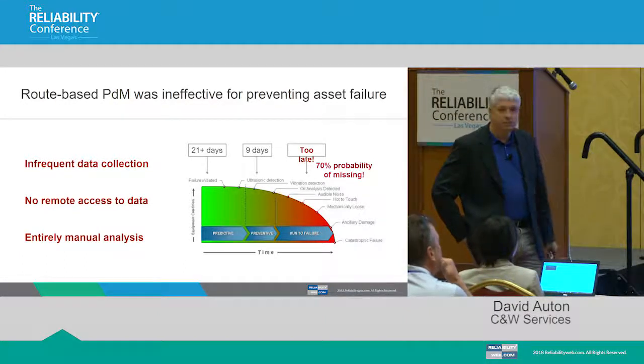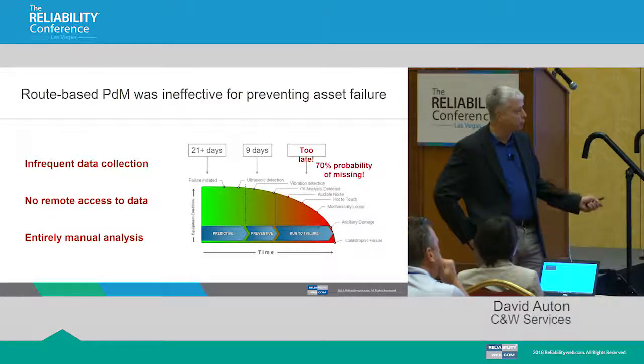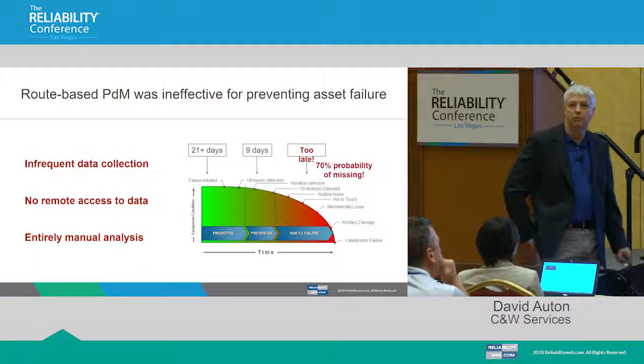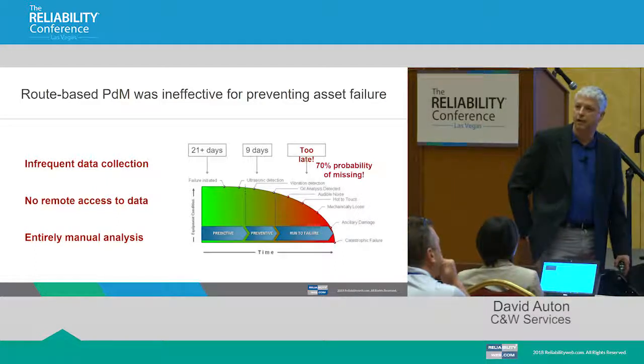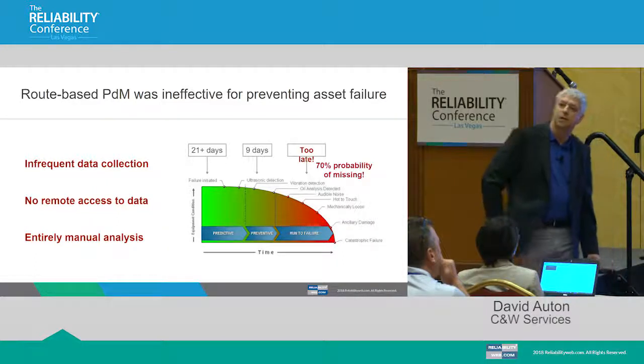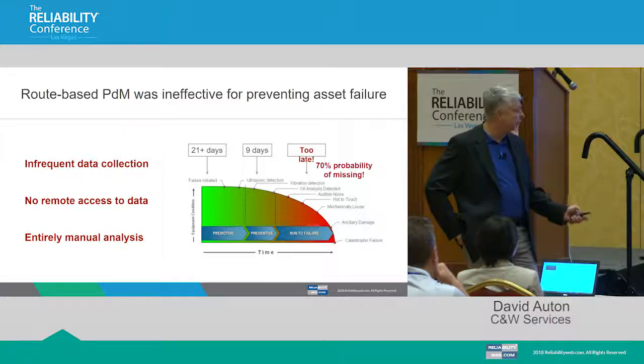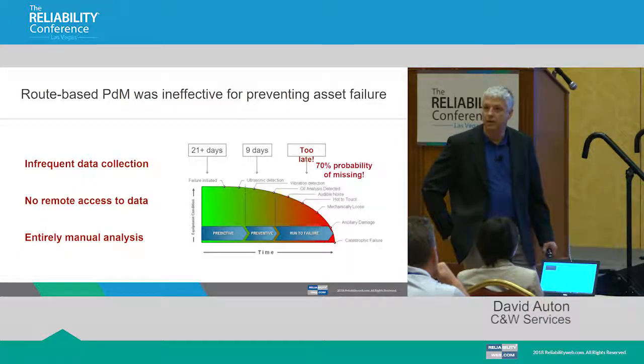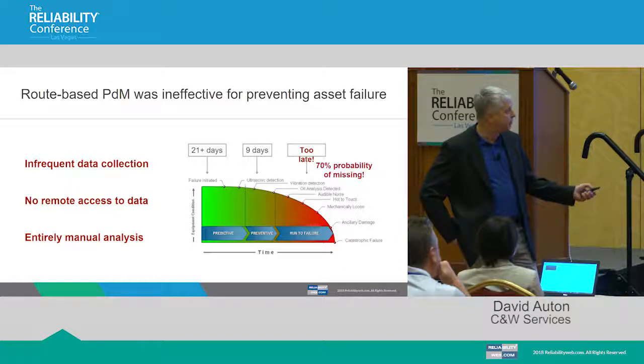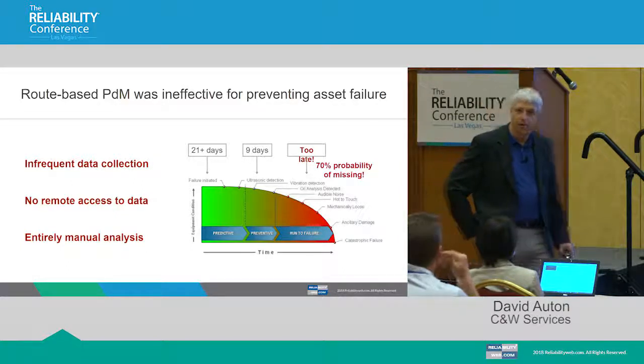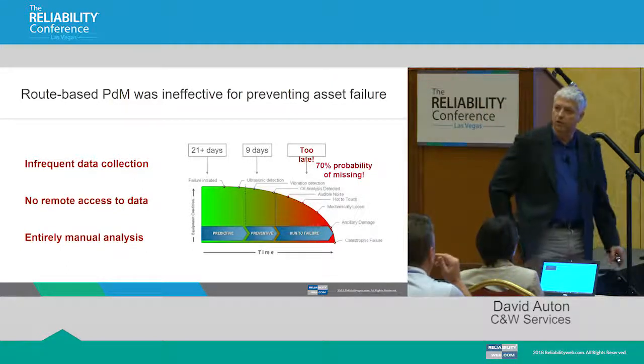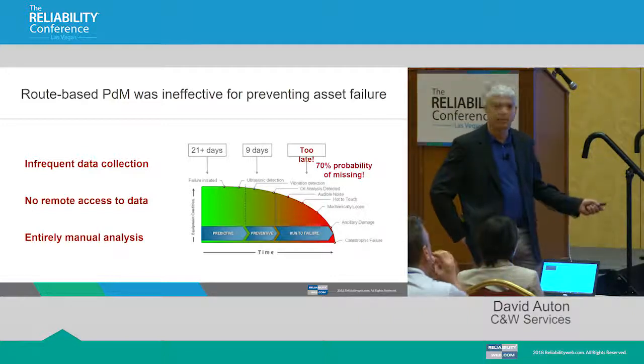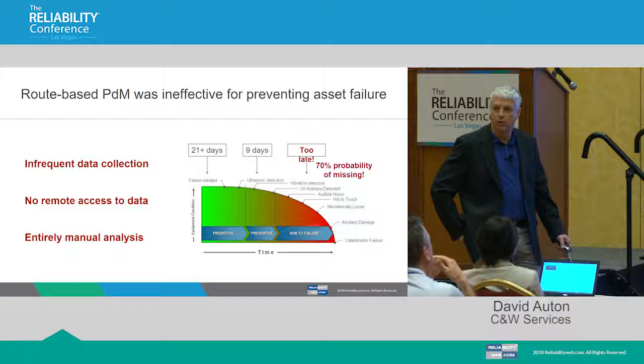So 70% of the time you're not going to measure it when it's in a failure condition if you're only doing it once a month. And so for our 350 units, we had 2 full-time guys going around getting once a month samples, and there's no way that I'm going to be able to add 6 more guys so I can get weekly samples. And even at weekly samples, you still have, what, 2/9 or 20% of the time you're going to be measuring it before it actually starts its failure, and by the time you get back to it again, it's past the point of no return, as it were.